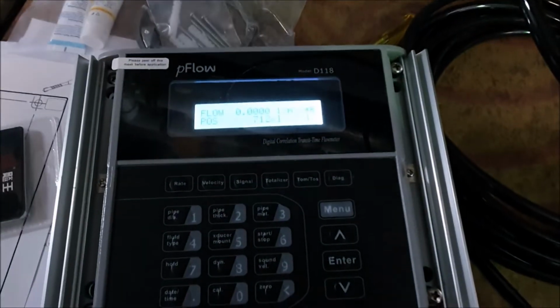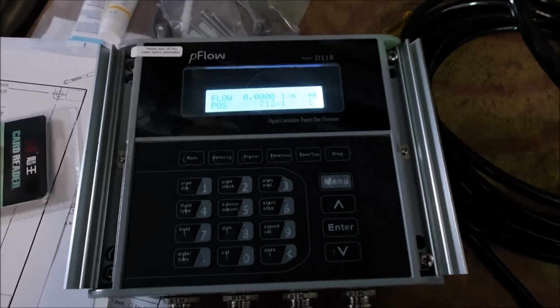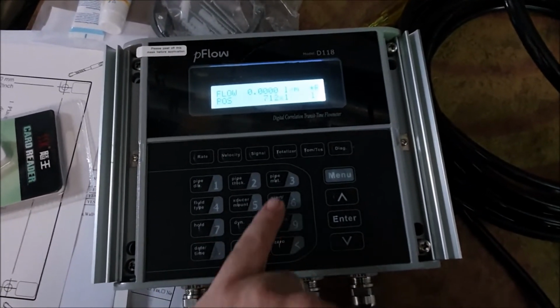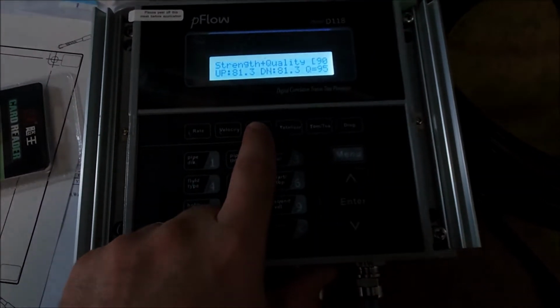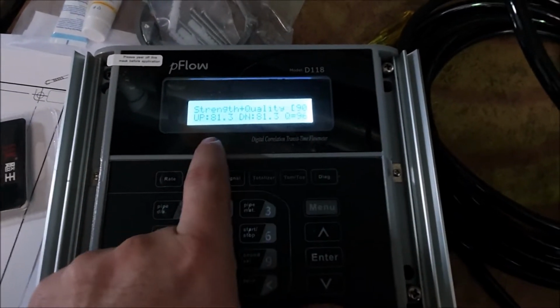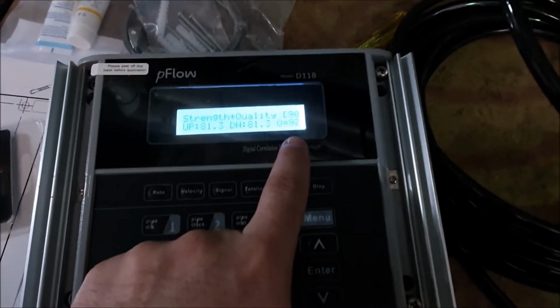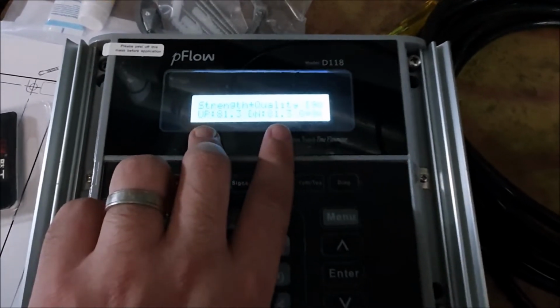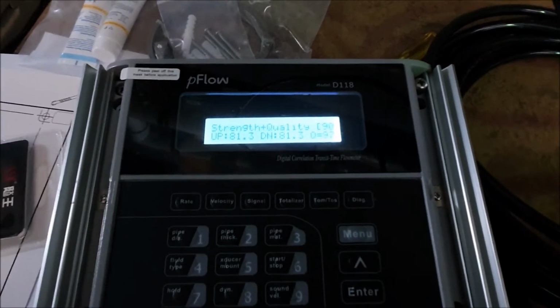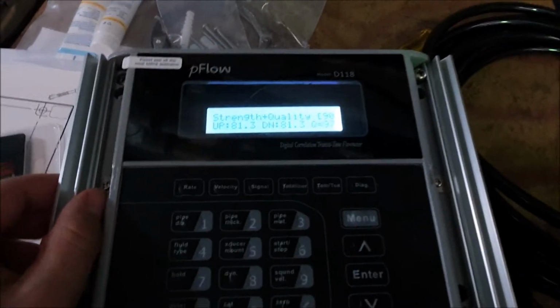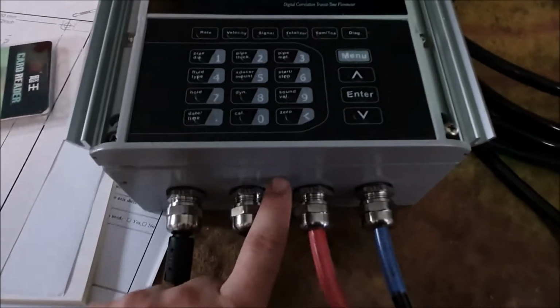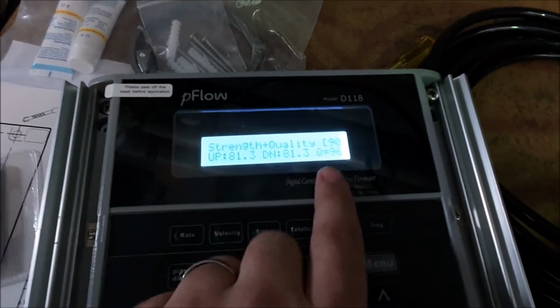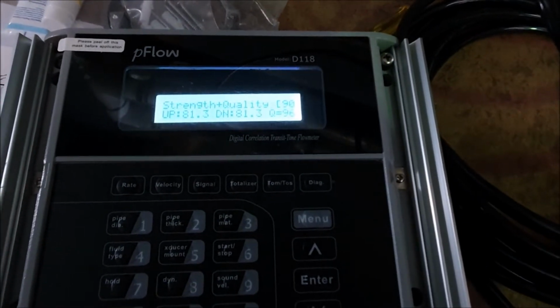Okay, so now that we've got the transducers mounted up, there's a few things we need to do to check our installation is good. So if we go to signal, you press this signal here, it'll give us a few values of interest. So you've got an up signal, a down signal, and a quality. These first two you just want within 10 of each other. If you have a larger than 10 differential, that may indicate you've got possibly a bad cable or a bad termination when we were putting the wires in earlier. But within 10 of each other on those first two, and this Q value is quality. You want to make sure that is probably about 60 or higher is good.